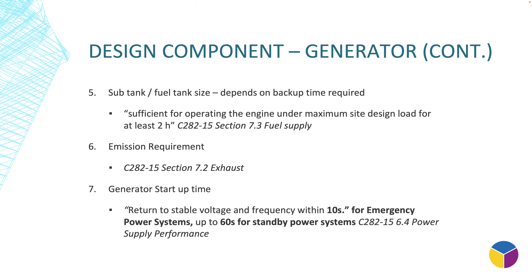You can do a backup time calculation — the diesel capacity calculation based on liters per second. Generator manufacturers provide this consumption information. Once you know the fuel consumption rate and backup time, you can calculate how much diesel you need. This is normally done by mechanical discipline, but as an electrical engineer it's easy enough for you to do as well.